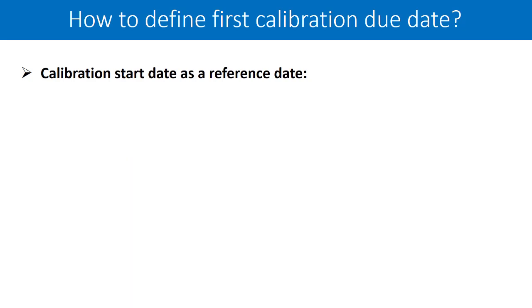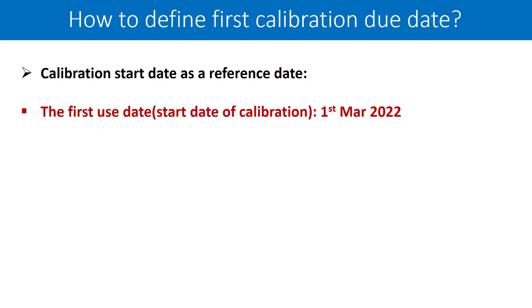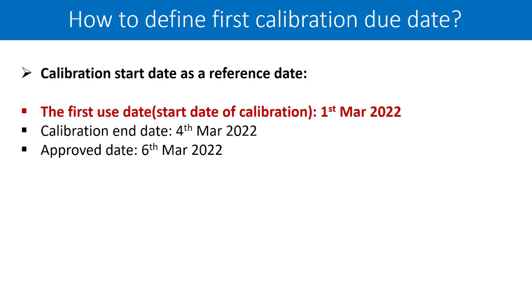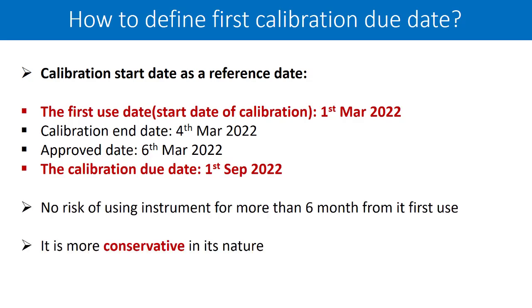Let us talk about the third approach — considering the calibration start date as the reference date. The first use date, or the start date of calibration, is 1st March 2022. Calibration end date is 4th March 2022, and the calibration approval date is 6th March 2022. If I calculate 6 months from the start date as my reference date, it becomes 1st September 2022. There is no risk of using the instrument for more than 6 months from its first use. This is the more conservative approach in its nature — I am not allowing usage of the instrument beyond 6 months from its first use.